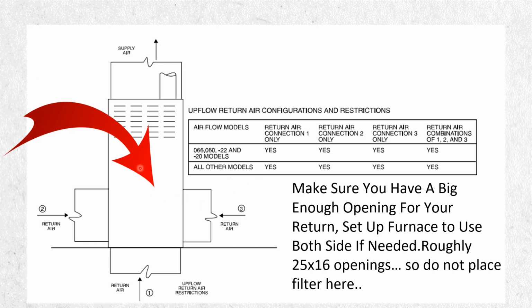A lot of the jobs that I go to, when I see this particular furnace in a vertical position, I always have a return duct right here on the side, and it's usually just one side because this is laying on concrete and this is probably a back wall or something, so they usually come out to one side, whether it be the right or the left. And this is common. Now on ICP, this is a 25 by 16 inch opening, and it will carry 2,000 CFMs. The problem is until you put a filter here.